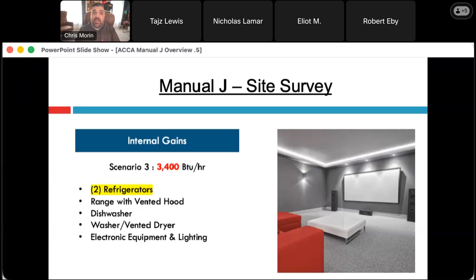Very common, you might have some ceiling fans. If you didn't realize, ceiling fans add about 250 BTUs per 75 watt motor within that space. If I have 2 ceiling fans in a living room, that's 500 BTUs. That can make a difference in sizing the runs on a duct system. So just make sure if you're doing a room by room load calc, you're making those adjustments to the correct space. And there's guidance within Manual J, and sometimes it's surprising. Sometimes you'll see a large family using TVs and stereos, computers, and laundry during mid-afternoon in the summer is an additional adjustment of 1400 BTUs for that load.